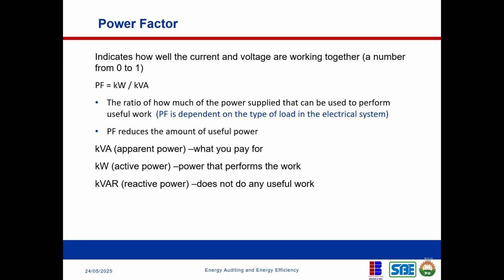For example, your generator can give 100 kVA. If you have a power factor of 0, that 100 kVA will give you 0 kilowatts. But as long as your power factor is not 1, it reduces the power you can get from that generator, from 100 down to maybe 80, 70, depending on where your power factor is. So we can understand how power factor reduces the capacity of our generator or transformer.